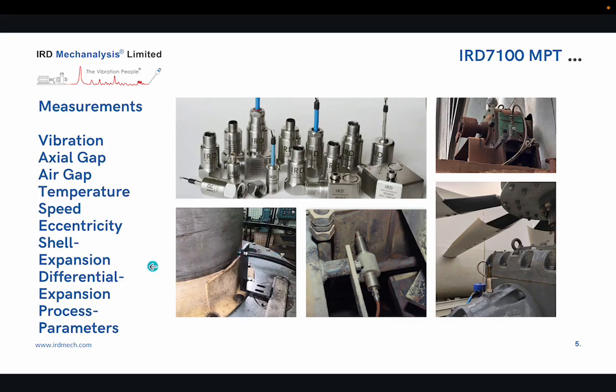Now, what are the kind of measurements that you can do using this product? So based on the order, based on the customer requirement, the product is factory configured to measure either vibration, axial gap, air gap, temperature, speed, eccentricity, shell expansion, differential expansion or other process parameters. In these photos, you can see the different types of vibration sensors. Another photo you can see a non-contact relative shaft vibration sensor. Another photo here you can see the LVDT measuring shell expansion, and another photo of a vibration sensor measuring the vibration in the vertical direction on a gearbox in a cooling tower fan.